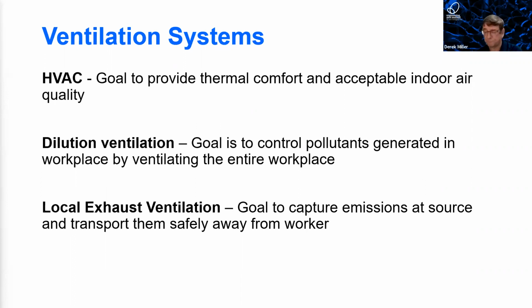Today we're concentrating on local exhaust ventilation. Notice the difference: we're not ventilating the whole workplace, we're trying to capture the contaminant at its source as it's released. Then we entrain it into the ducting system. As it travels through the duct, an LEV system makes sure the contaminant doesn't settle out and cause problems, eventually reaching the baghouse or whatever filtration system we have in place—precipitators, etc.—and then fresh air goes back out.